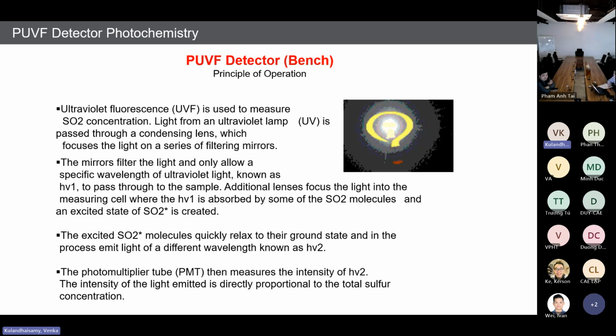Pulsed means the UV lamp will not be on continuously. It will flicker 10 times in 1 second. That means on, off, on, off, on, off, on, off. So with this on-off signal, we are able to eliminate the noises. Also, we are able to eliminate other elements apart from SO2. That's why we are using this PUVF technology, pulsed ultraviolet fluorescent technology.